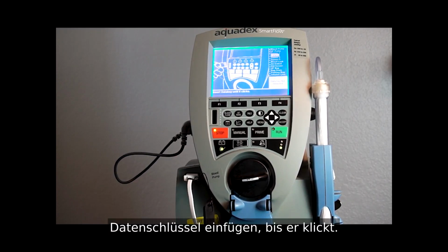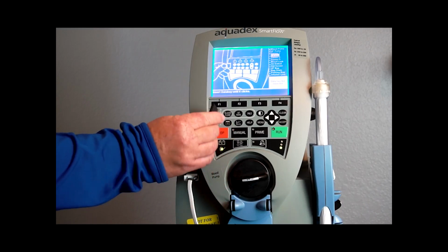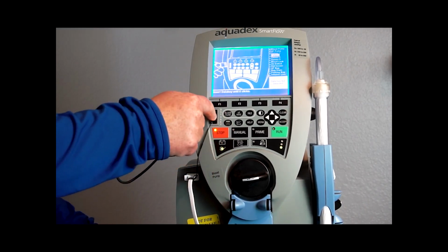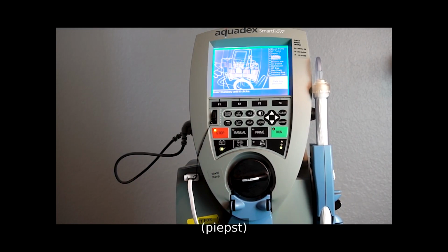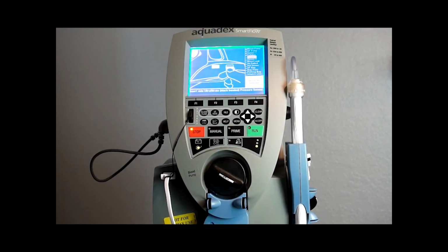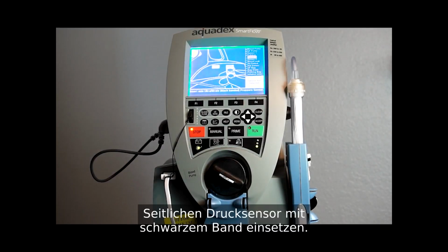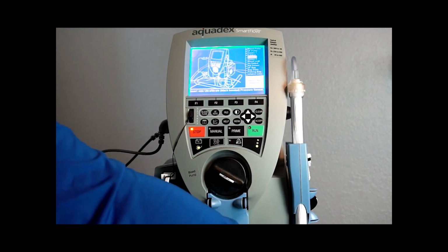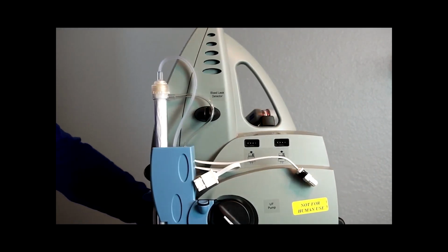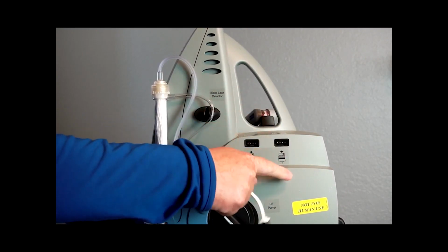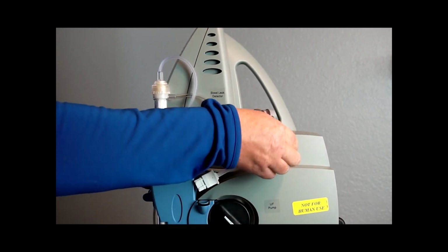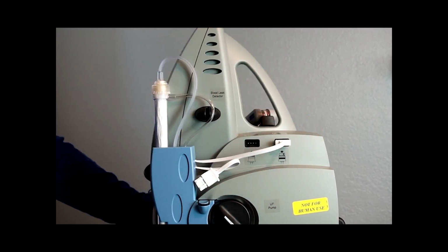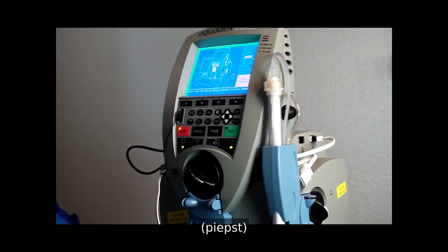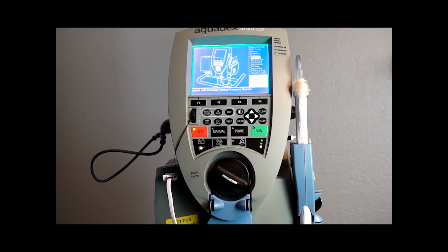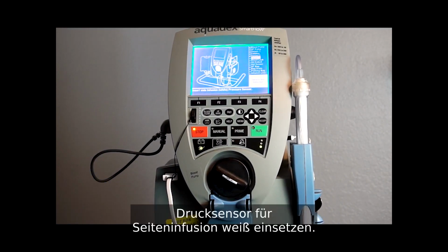Insert data key until it clicks. Insert side ultrafiltrate black banded pressure sensor. Insert side infusion white pressure sensor.